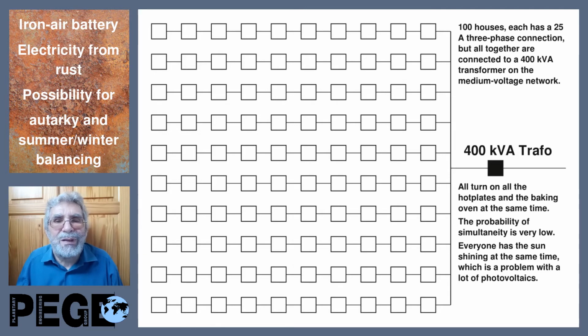Yes, the problem is at the same time. It's not very probable that in all the kitchens, all the hot plates and the baking oven are turned on at the same time. When this would happen, sure, the grid in this small village would go down. But because the probability that this happens at the same time is very low, they take only a 400 kilovolt-ampere trafo and everybody is happy.